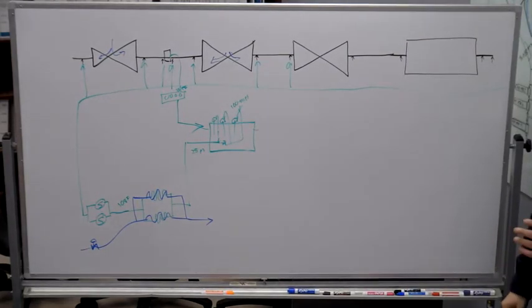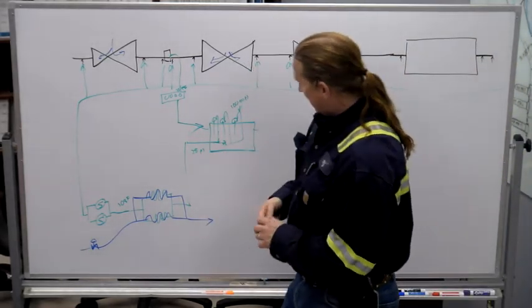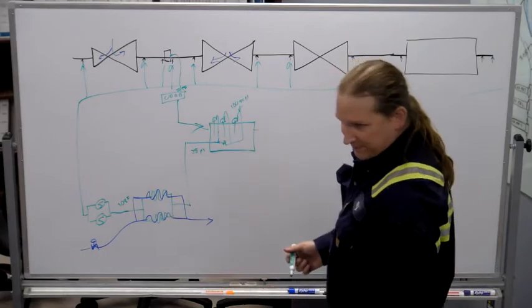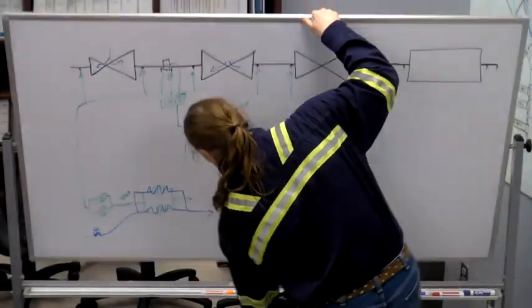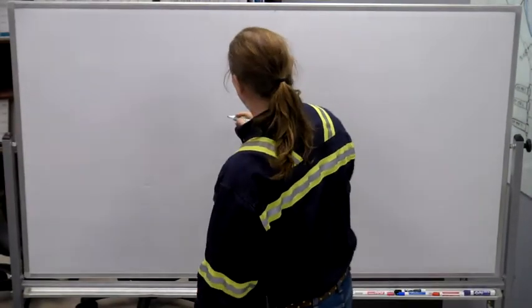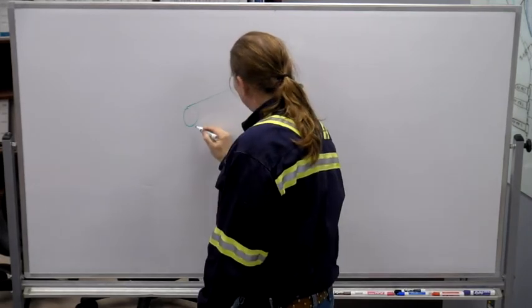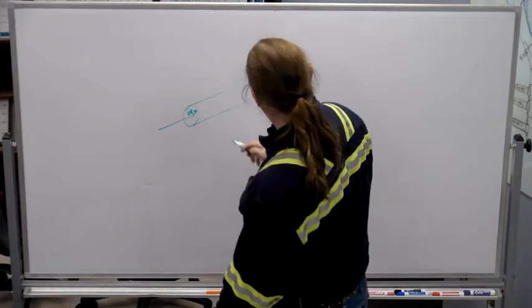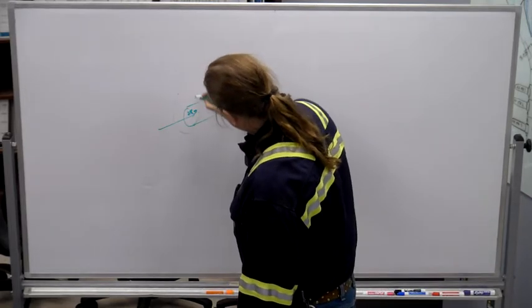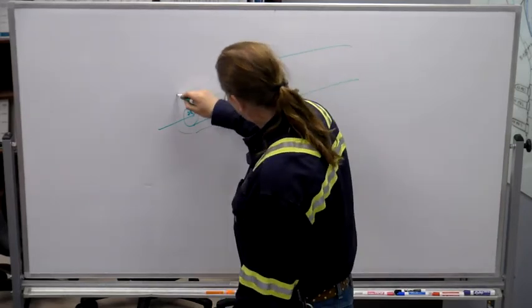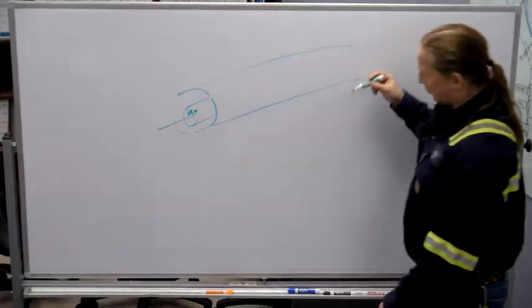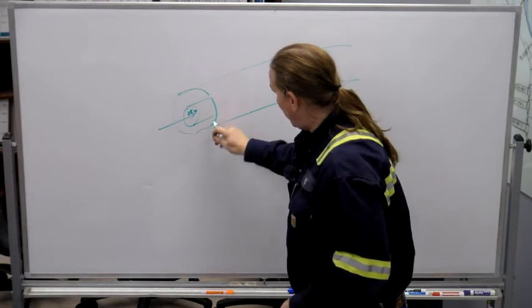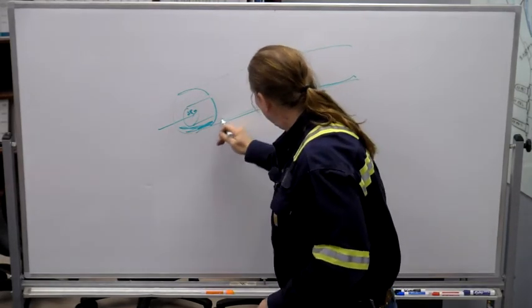When you try and walk this down, it is very challenging because they have a concentric piping system. Concentric means it has the same center, and that means you've got a pipe inside a pipe. So you come from the pump and you go in there and that's your 28 psi, and that is full flat up with oil. And then on the outside of that, the return header is actually the same pipe except bigger. So then the oil there is not filling up that whole thing, it's just draining in the bottom and making its way back to the tank.